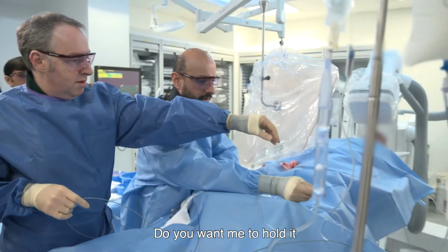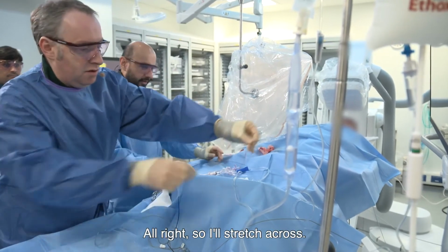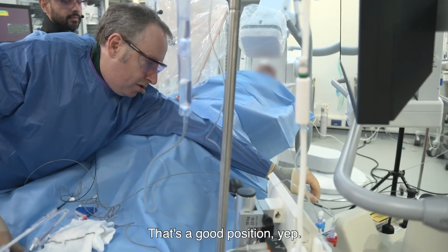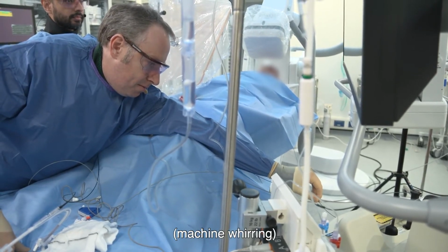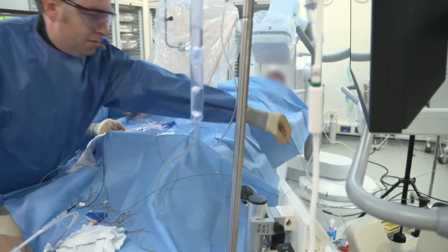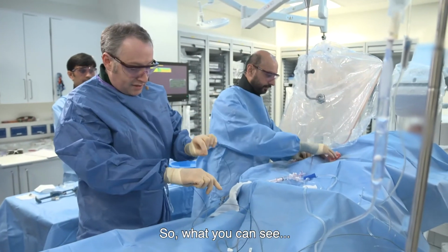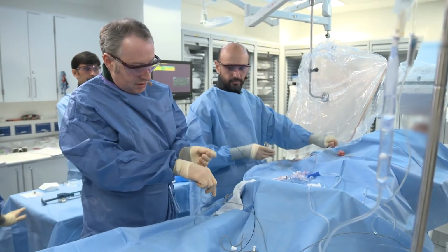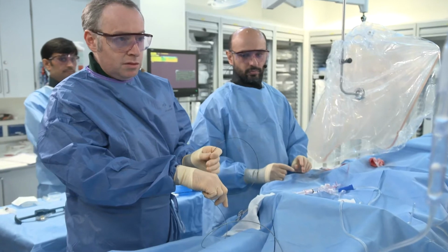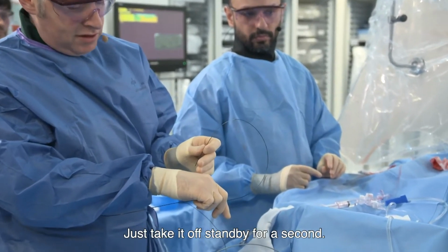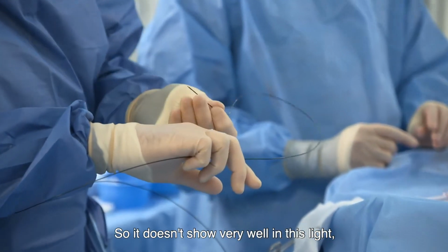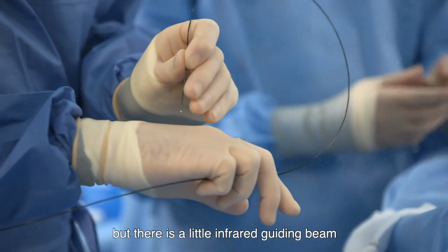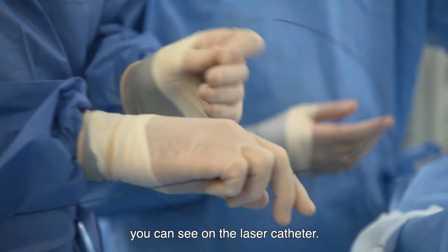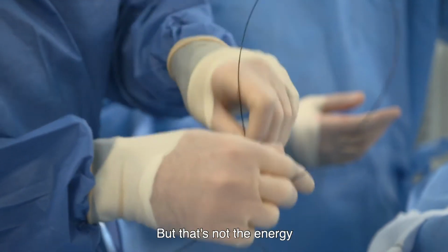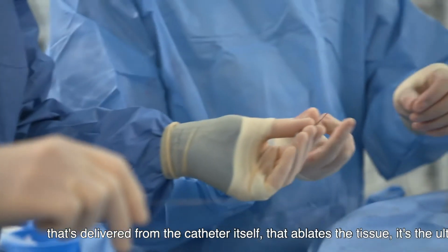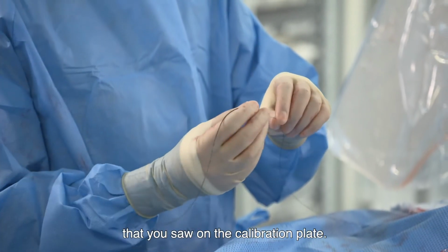Do you want me to hold it, and maybe you activate the pedal? All right, so I'll stretch across. That's a good position. Yep. Perfect. So, what you can see is laser catheter on. Yeah. Just take it off standby for a second. It doesn't show very well in this light, but there is a little infrared guiding beam that you can see on the laser catheter, but you can't really see it on my hand at the moment. But that's not the energy that's delivered from the catheter itself that ablates the tissue. It's the ultraviolet light that we saw on the calibration plate.